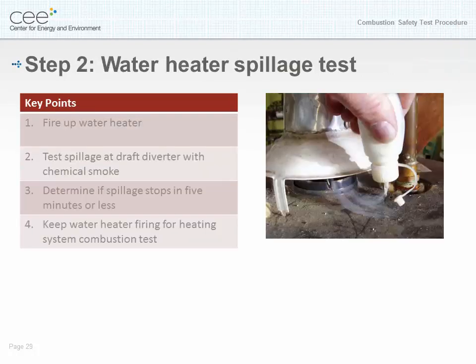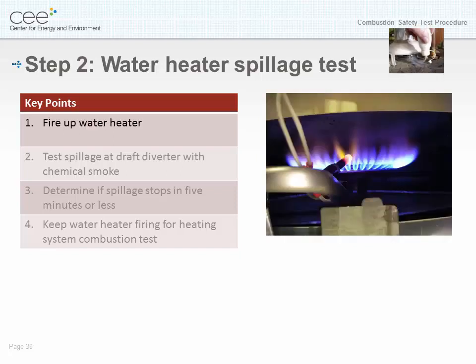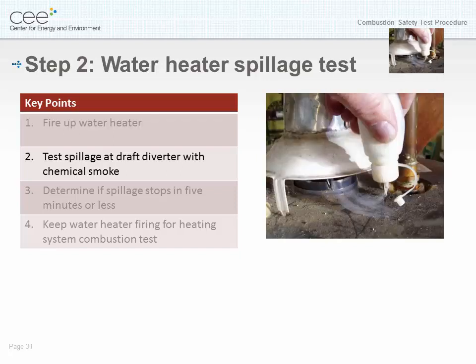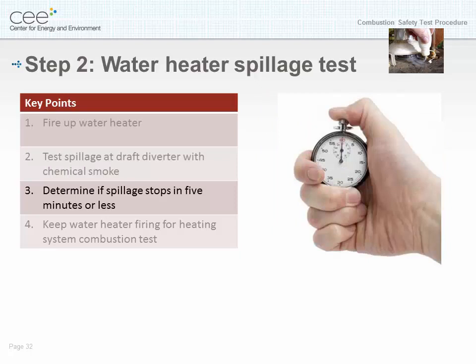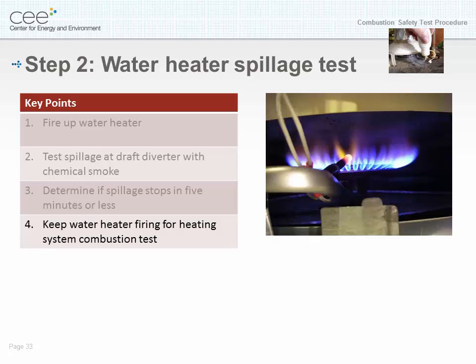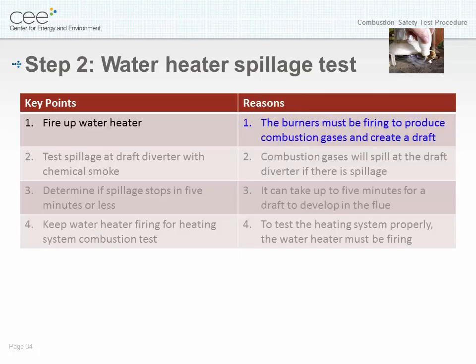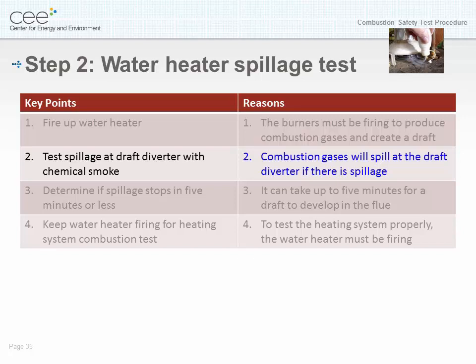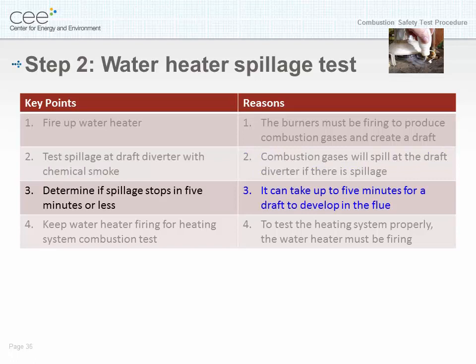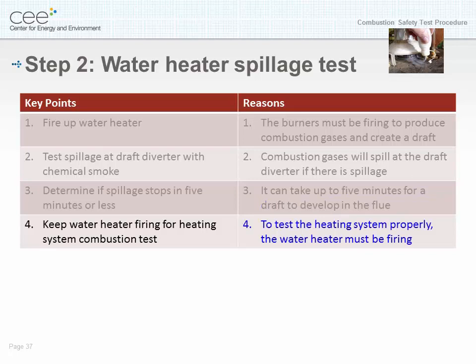Step two: water heater spillage test. Key points: number one, fire up the water heater; number two, test spillage at the draft diverter with chemical smoke; number three, determine if spillage stops in five minutes or less; number four, keep the water heater firing for the heating system combustion test. Reasoning: the burner must be firing to produce combustion gases and create a draft; combustion gases will spill at the draft diverter if there is spillage; it can take up to five minutes for a draft to develop in the flue; and to test the heating system properly, the water heater must be firing.